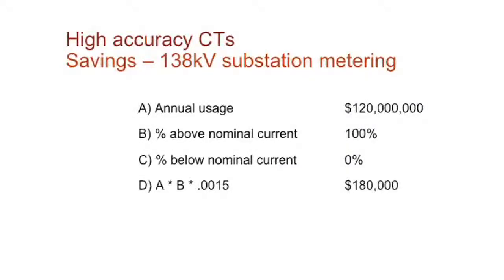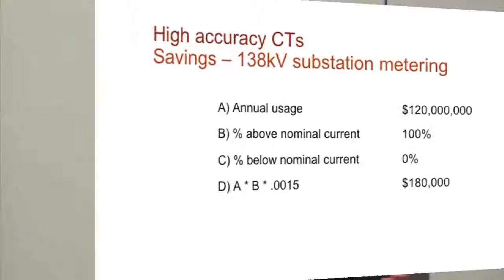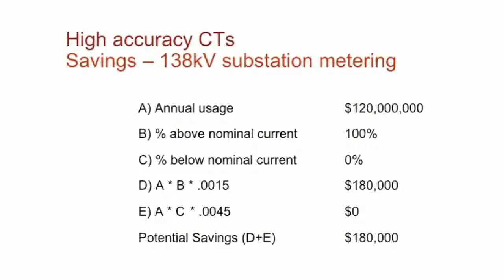The difference between 0.3% of revenue grade metering and then high accuracy metering. Most of these though already have high accuracy metering, so this wouldn't be something the utility would typically say, I need to add this, okay, I need to change this. Usually it's already metered at that level with high voltage instrument transformers, but I just wanted to show, as you scale up the amount of electricity that you use, you can really start to save a whole lot more money, and that's really where your cost driver is going to be.